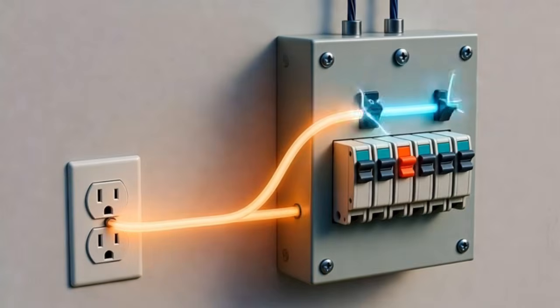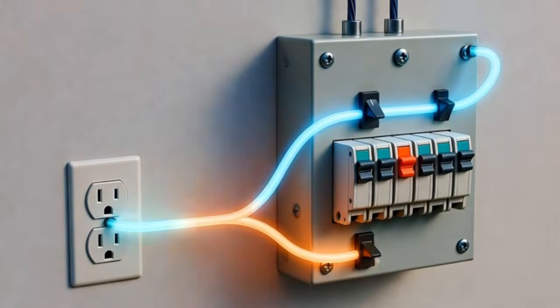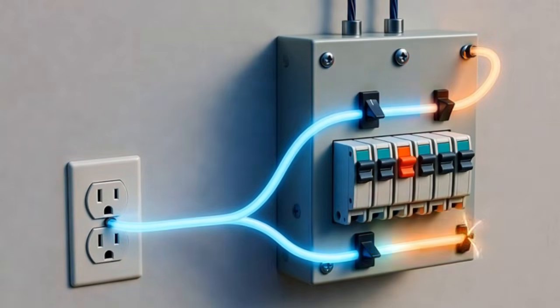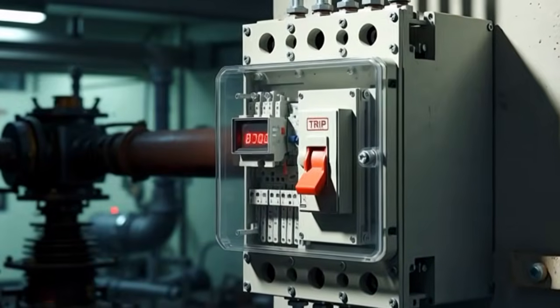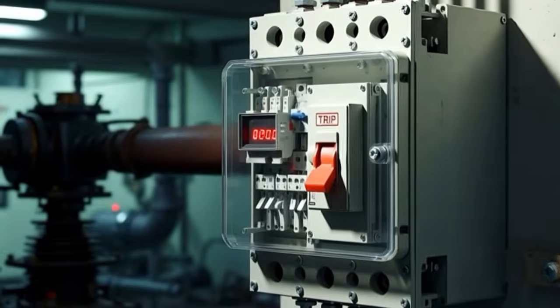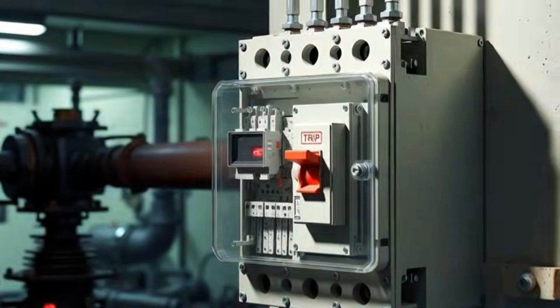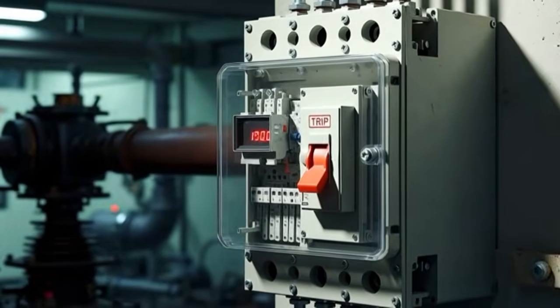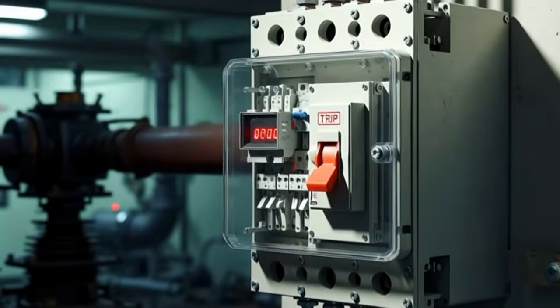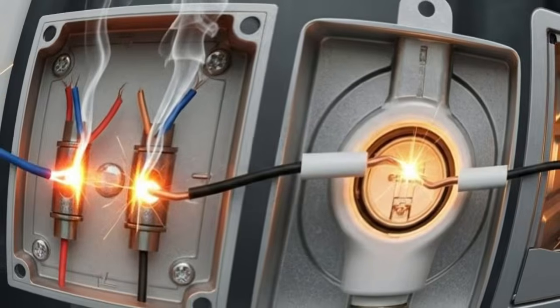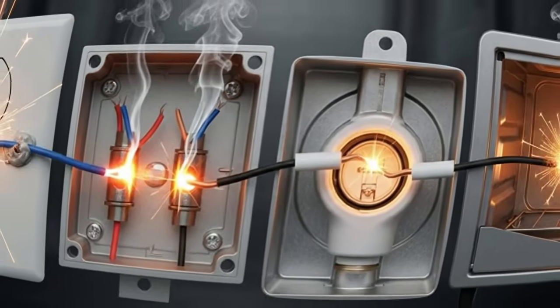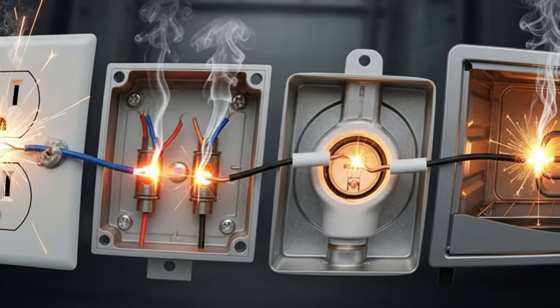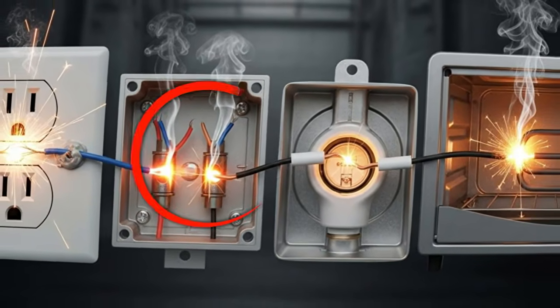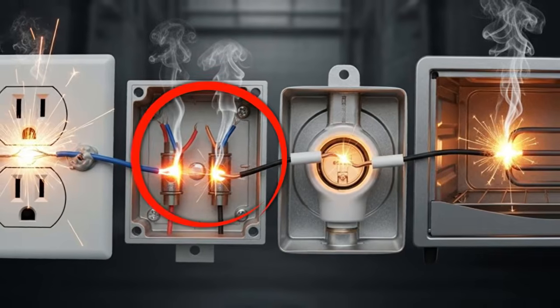The breaker's electromagnetic coil detects this surge and trips the breaker within milliseconds. But here's why the breaker won't reset. The short circuit is still there. The wires are still touching. As soon as you close the breaker, current rushes through the short again, and the breaker trips instantly. Short circuits happen inside outlet boxes, junction boxes, light fixtures, and appliances. Damaged wire insulation is usually the culprit.